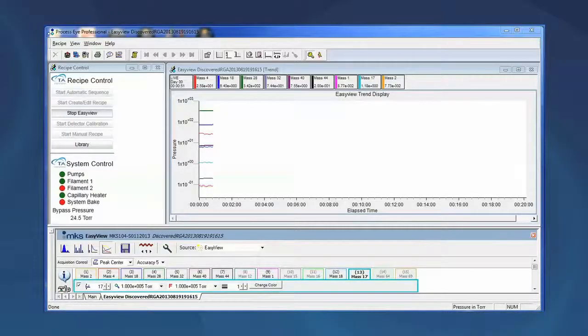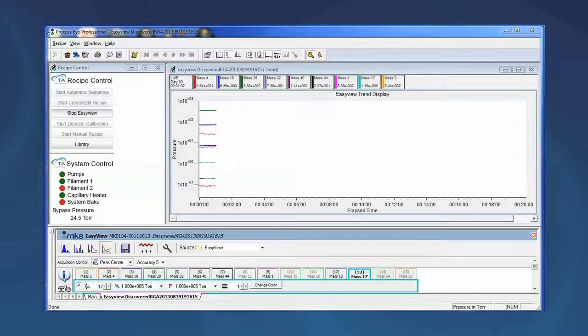In our last tech tip we introduced the easy view mode and the bar chart and peak jump trend windows. In this tech tip we will use these tools as a basic check on the instrument performance, as well as to identify any ions present in the background of your mass spectrum. In the last tech tip we showed a very quick way to check the detector response by simply breathing into the open TGA furnace and observing the response of the carbon dioxide and water peaks.